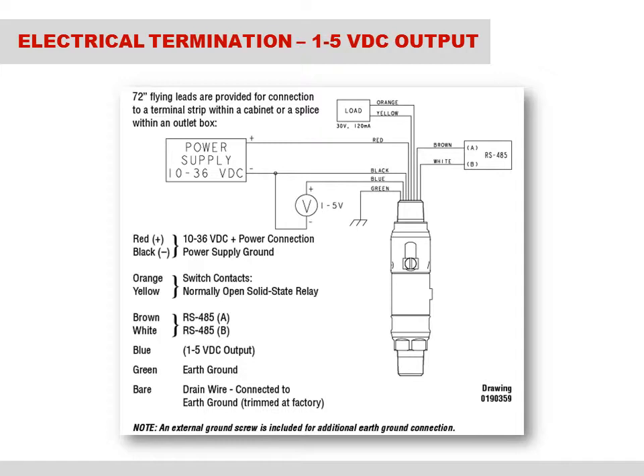As before, it is not necessary to terminate all 8 conductors. It is okay to terminate only the wires that are required for your specific application. Also recall that one should not cut and discard unused conductors. Instead, protect and safeguard all unused conductors for future use of the specific functionality that is available via those conductors. Always properly ground the 815 PT instrument using the green insulated conductor.